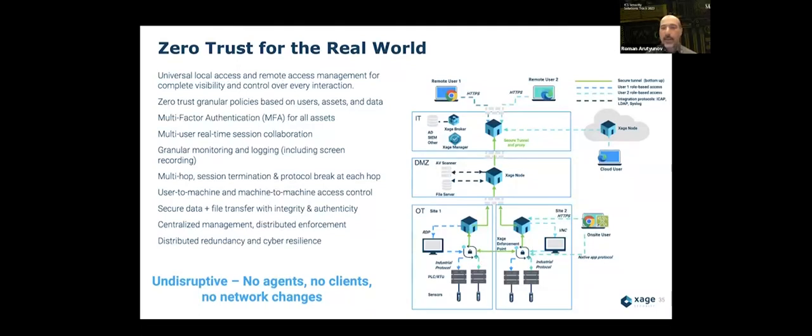Each node in the architecture is an authentication, authorization, and enforcement point, meaning that users that need to interact with assets would use the local nodes in those environments to essentially access the asset through that portal, authenticating with the Xage node using their real identity with multi-factor authentication and optionally multi-layer multi-factor authentication, which ensures that separate identities can be used at each layer of the architecture with separate MFA seeds as well.